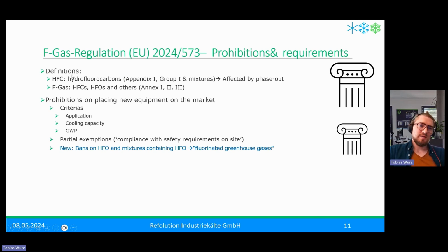I mention it again because it's very important to understand that the regulation has two definitions inside, especially in the chapter on placing new equipment on the market prohibitions. We have HFCs, the hydrofluorocarbons, that are affected by the phase out, that are limited, and where we expect this major price increase. And we have the F-gas group that includes these HFCs, but additionally the HFOs and some other gases listed in the annex of the F-gas regulation.